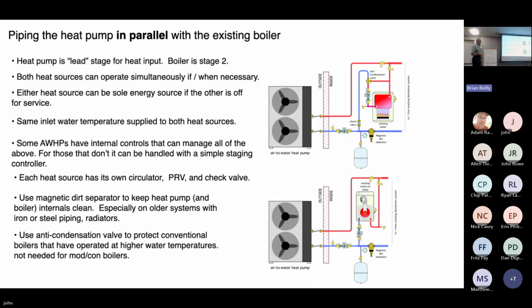Okay. I come in parallel. I like to use magnetic dirt filters. There's several on the market now. This will collect what's called magnetite. That's basically very, very fine particles of iron oxide. If you've got cast iron radiators or steel pipe or cast iron circulators in the system, there's a chance you're going to have some residual magnetite in the system. And you don't want that inside the heat pump. It just coats the surfaces of the heat exchanger.